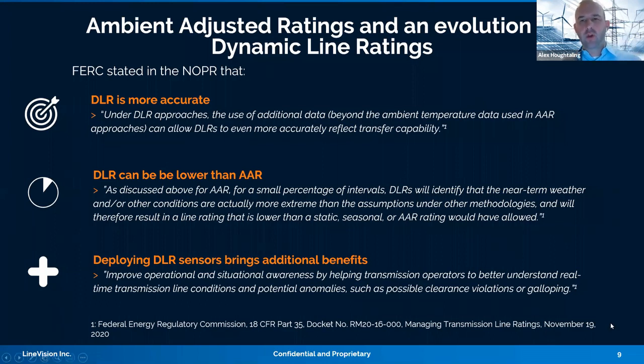As I mentioned earlier, DLR can sometimes be lower than ambient adjusted ratings or the static line rating. So there's really an emphasis on the safety of your transmission lines and the security of the system, insofar as adopting these advanced technologies gives you the upside of more capacity, but also reduces the risk in those moments where the actual advanced line rating falls beneath the static line rating.